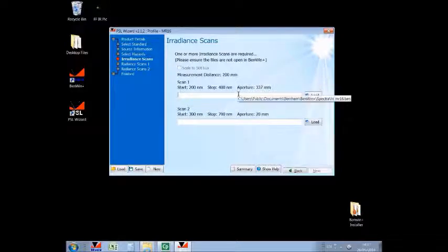The UV and indeed the infrared eye should be performed in a field of view less than 1.4 radians, and that's to effectively account for the fact that the eye is protected by the structure of the nose and the bridge of the eye, etc. So any radiation outside the 1.4 radians or 80 degrees need not be considered. This aperture is calculated based upon 200 millimeters and 1.4 radians. And equally for blue light exempt risk group, we talked about before about 100 milliradians at 200 millimeters is a 20 millimeter aperture. So you'd effectively need to load two separate measurements.